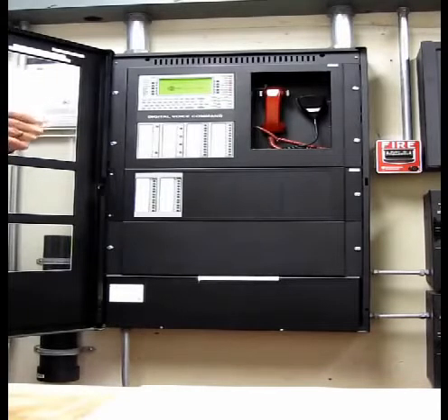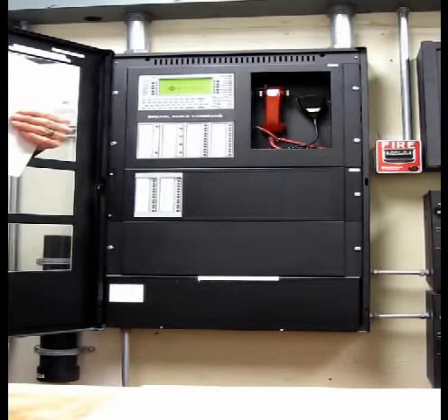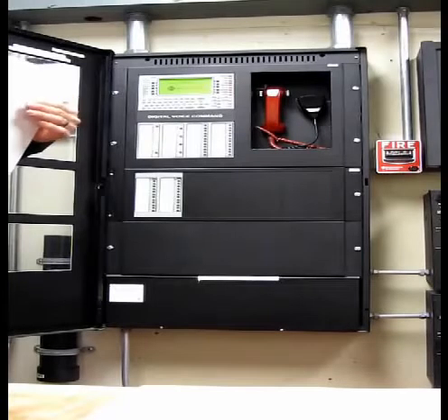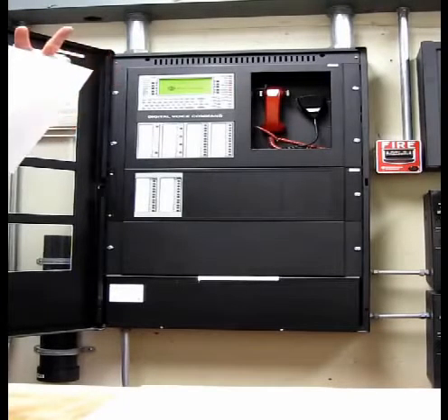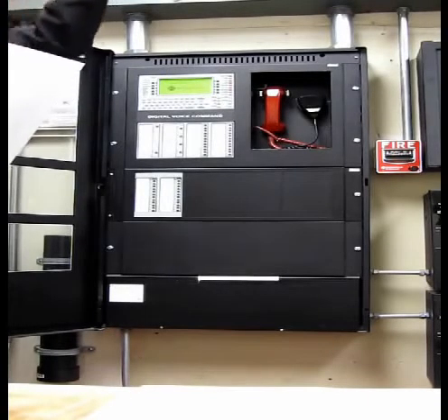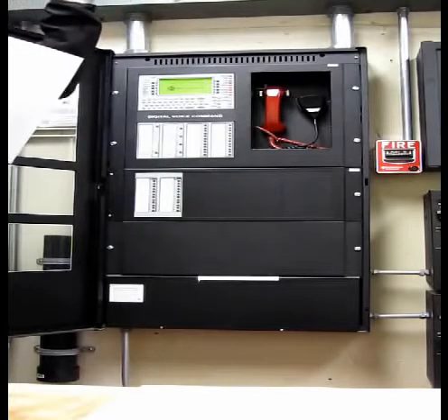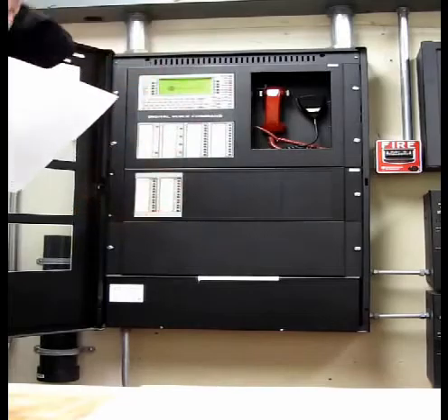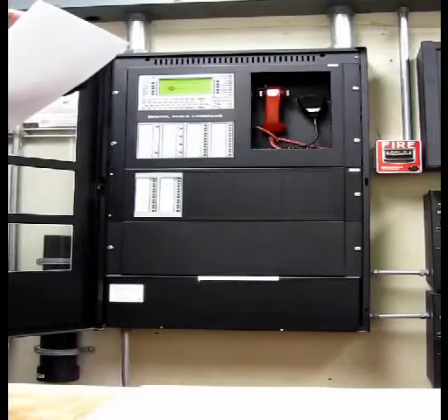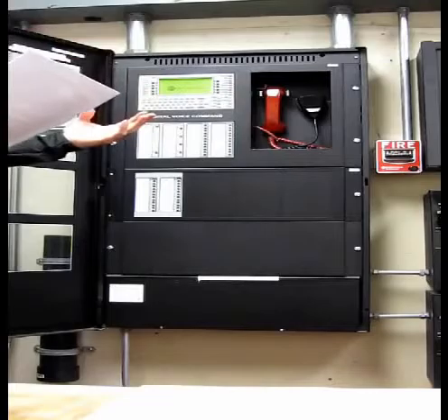Okay. So for the supervisory conditions, once again, it's just for the sprinklers and then for the smoke detectors? Smoke detectors in the guest rooms only, and the sprinkler tamper valves. A sprinkler water flow, there's 2 different devices on a sprinkler system. A water flow is basically like a switch that's inside the pipe. Once a sprinkler head breaks, the system's always got water in it, in the sprinkler system. So once a head breaks, that water is escaping, and when the water is refilling itself from the city, there's a switch inside the pipe, a little flapper valve that after, between 30 and 90 seconds, that flapper valve is activated from the water flow, and that's a full-blown alarm.